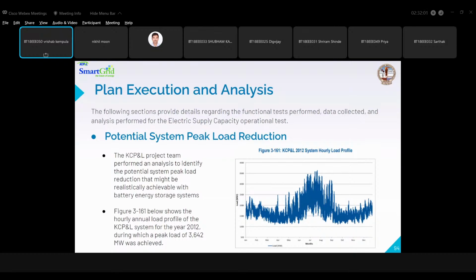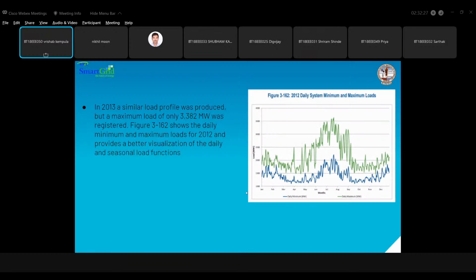Here we perform an analysis to identify the potential system peak load reduction that might be realistically achieved with the battery energy storage system. This shows the hourly annual load profile of the KCP&L system for 2012, during which a peak load of 3,642 megawatts was achieved. Coming to 2013, a similar load profile was produced, but a maximum load of 3,382 megawatts was registered.